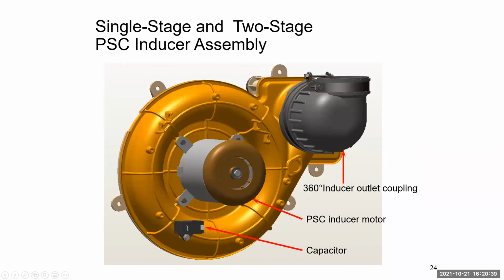Single stage and two stage inducer assemblies. Again, nothing new. Kind of a refresher for those that might not know or are newer into this. Your exhaust boot is 360 degrees. It can go in any orientation you want, up, right, left, down. Make sure that if you do adjust it, you retighten your strap or it's going to come off eventually with vibration.